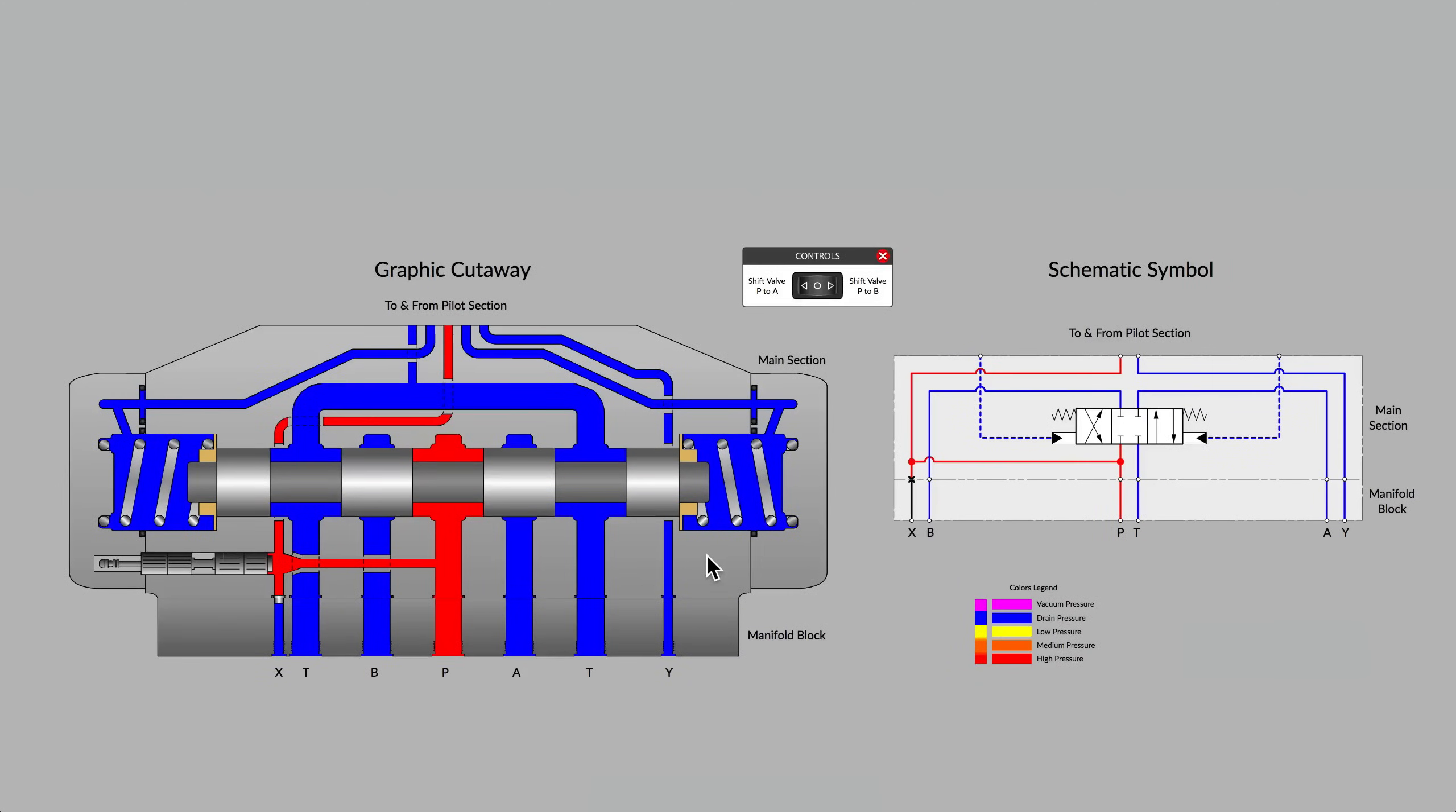The question sometimes asked is why not just install solenoids at both ends of the main spool. The reason that is not done is that the size of the winding would be very large and the amount of electrical current required to create the magnetic force to move such a large spool would be very inefficient. So pilot pressure is brought to bear on the right-hand pilot head or the left-hand pilot head to move the valve. But in simple terms, it is just a basic spool-type directional control valve.